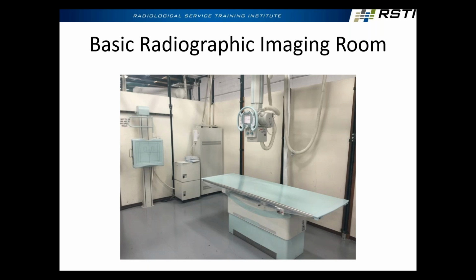So once I have everything lined up, if I have something like a PBL collimator, like this one here, PBL stands for positive beam limitation, which is a fancy way to say an automatic collimator, right? So if I were to take my image receptor, pull out this cassette tray, put it in there, lock it into place, when I push that in, it's actually measuring the size of this. And it will tell the system what size that receptor is, and this will automatically size right down to that area. So I'm only exposing that area. Yes?